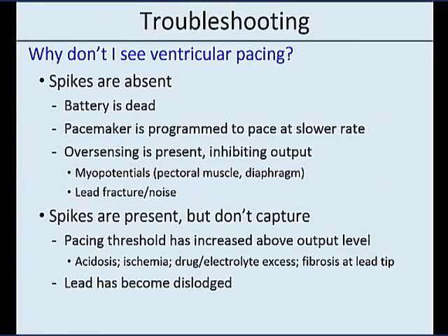You may also have oversensing. It may be programmed to pace at a certain rate. You're seeing it going lower than that rate, but it is inhibited by something it's seeing. For instance, myopotentials. This is not too often seen in the hospitalized patient because they're not moving around so much. But a lead fracture can also cause a make-break noise on the lead and make it look to the pacing system like there is a QRS complex when there really isn't.